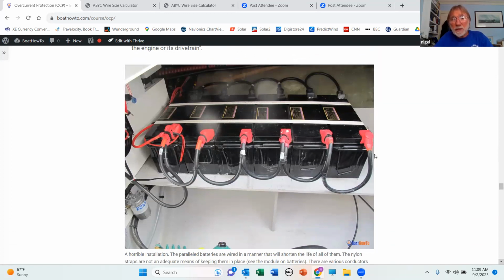We've got 6 batteries in parallel. We've gone from positive to positive to positive to positive to positive, and then negative to negative and all the way out. First of all, there's no way this strap is adequate restraint. If it gets into seriously rough weather, those batteries are going to be bouncing around all over the place. Secondly, if we look at the overcurrent protection, we've got all kinds of conductors.